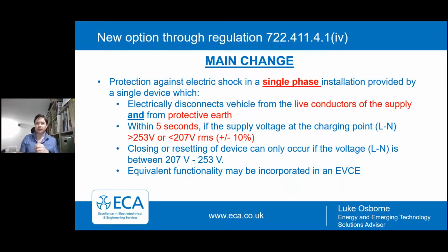So you have a new option in Amendment 1, and this was through indent 4 of 722.411.4.1. And this allowed you to provide protection against electric shock in a single phase installation through a single device which disconnects the vehicle electrically from the live conductors of the supply and the protective earth. This needs to operate within 5 seconds if the supply voltage at the charge point is above 253 volts or below 207 volts. This can only close or reset if the voltage is back within its tolerable area, and equivalent functionality of this may be incorporated into the electric vehicle charge point itself.